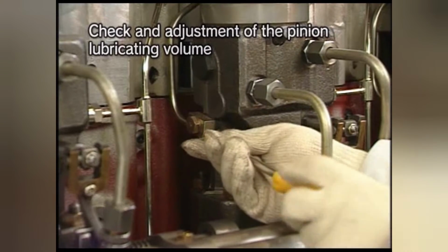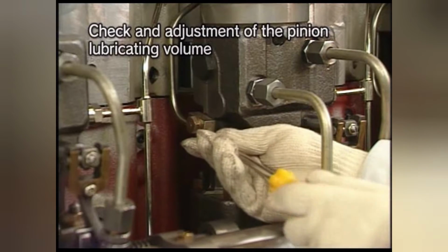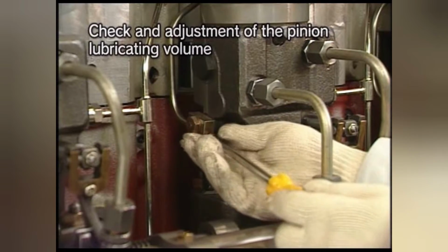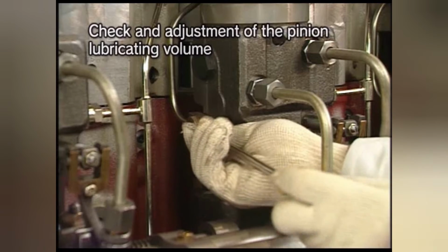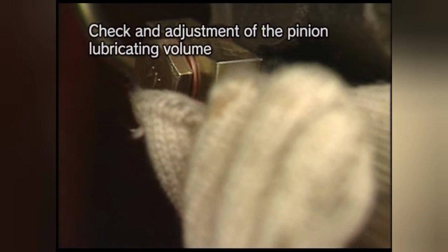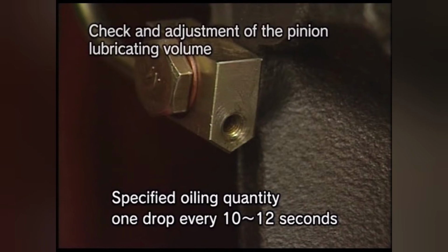Check the oiling quantity by the quantity of the oil dribbling from the plug after removing the plug screw for the check of drop quantity on the side of fuel injection pump. Check that the oil drops at the rate of 1 drop every 10 to 12 seconds.